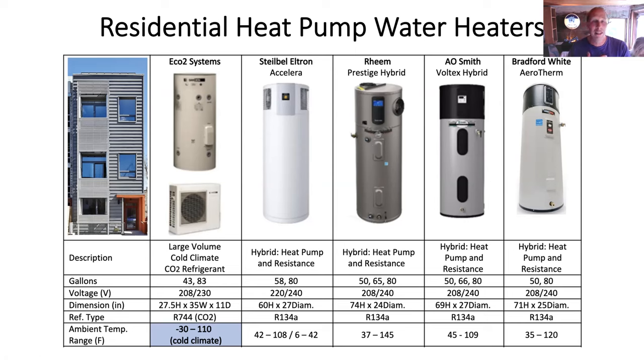We've studied this in 23 apartments, including households of 7 people down to fewer, and found that tenants got better service if they stored hot water than if they had the 30 amp, 5,000 watt version, the high electric resistance mode, which provided worse service. Electric resistance isn't as good as more hot water at giving you shower after shower after shower.